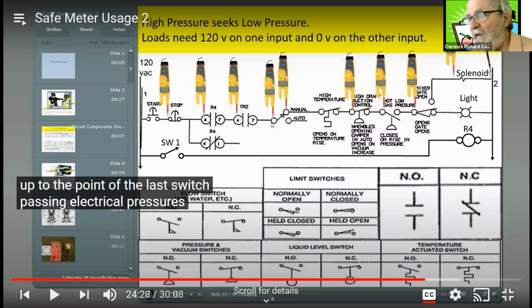If we get to this point right here, we've got a manual auto switch. We better have that thing in manual if we're going to get to the next step. Then we get to this high temperature rise. This could be the temperature switch in your burner control. That's going to shut down your plant if your bags start going over 400 degrees. If it goes over 400 degrees, the temperature switch is going to open up. So you've got to be under 400 degrees to continue to go through.